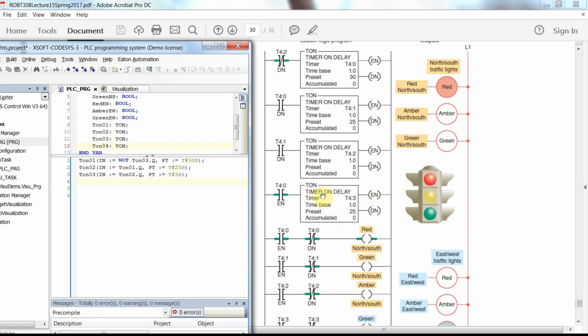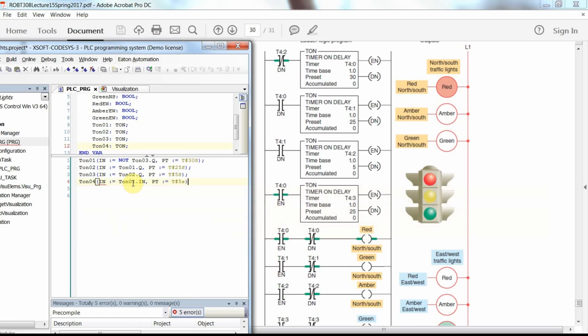For the fourth on-delay timer, the input comes from the enable bit (IN bit) of the first timer, so we write T04 with IN equal to T01.IN, and the preset time PT is T#25S.